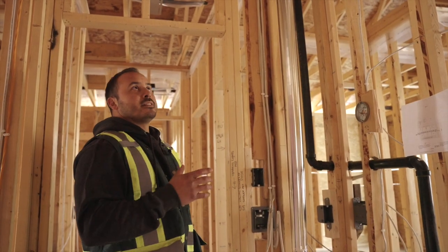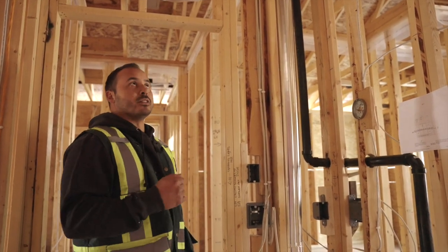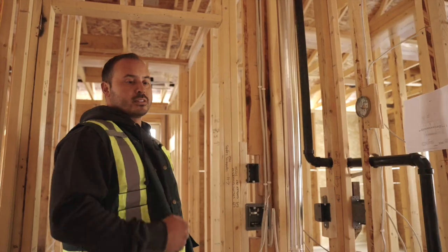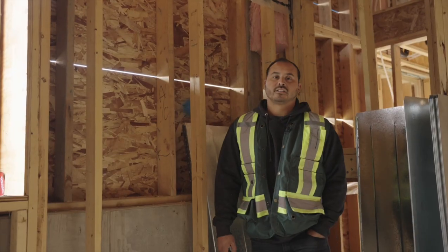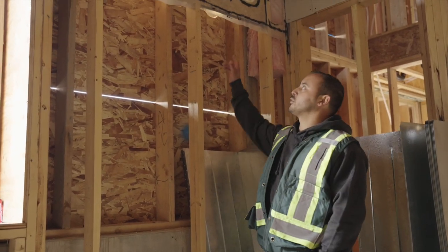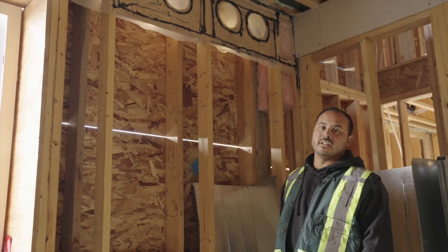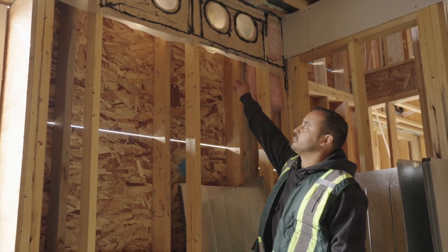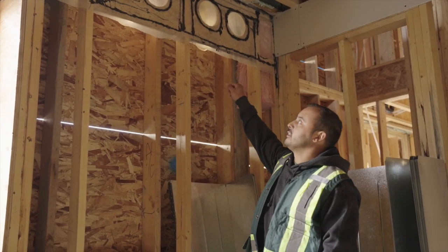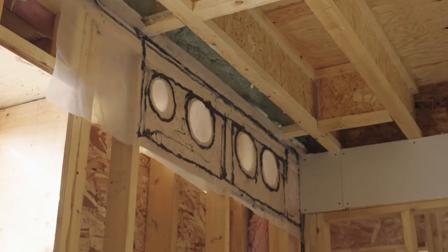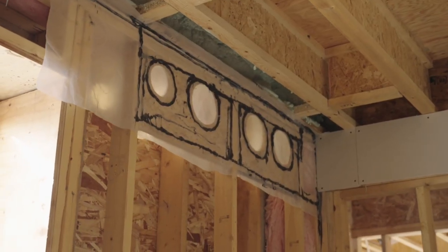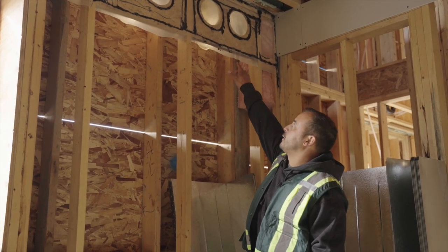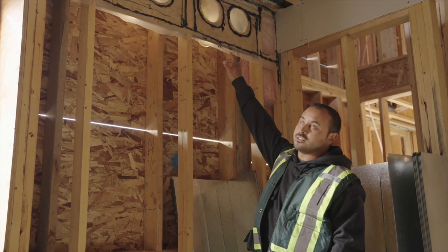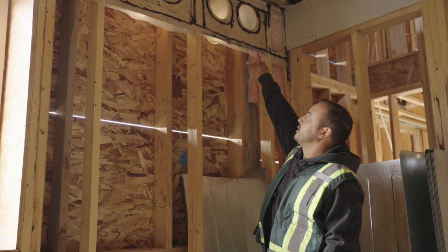Using this type of system eliminates the amount of penetrations through the vapor barrier, through the roof, and through the ceiling and walls. A lot of considerations are taken before holes are punctured through the vapor barrier and exterior walls. Our team, and every team doing an HVAC installation, needs to consider what this backing looks like. This way everything is sealed, with solid backing surfaces for the vapor barrier to be sealed to, and then a small area just for ductwork to pass through.